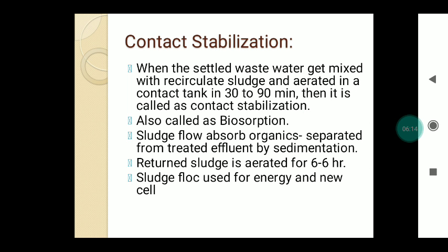Next one is the contact stabilization. When the settled wastewater gets mixed with the recirculated sludge and aerated in a contact tank for about 30 to 90 minutes, it is called contact stabilization. It is also called biosorption because the sludge flocs absorb the organics, and it is separated from the treated effluent by the sedimentation process.